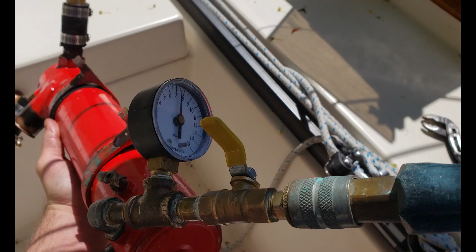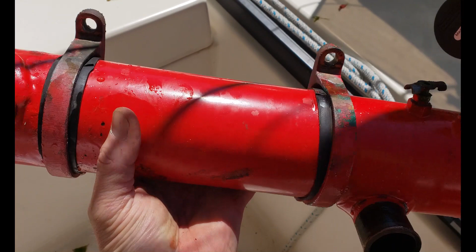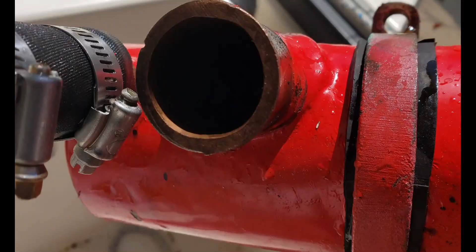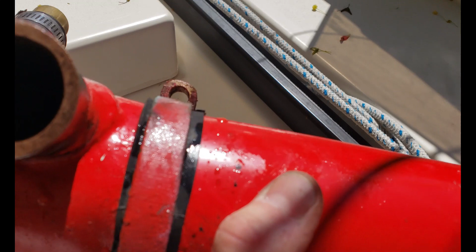Alright, I'm going to try to hold this one-handed. I've got an air line with 120 psi, but I just used that valve to bleed in about 6-7 psi. I don't know if you can hear this, but it's definitely leaking, I can hear it. These would be the coolant side, the two open ones. I've got the raw water side plugged off, but I can hear it leaking. So, heat exchanger's effed.